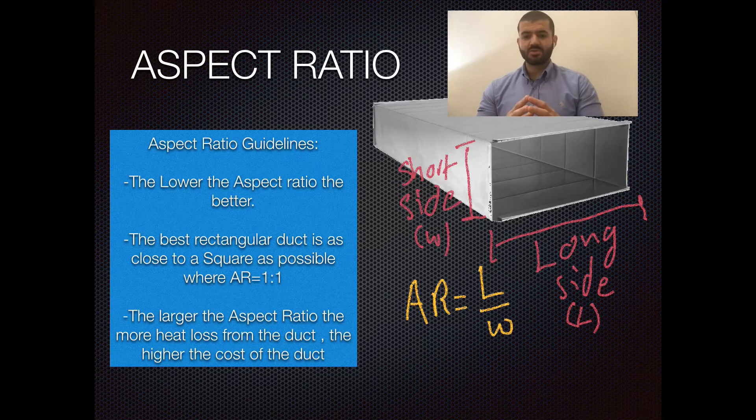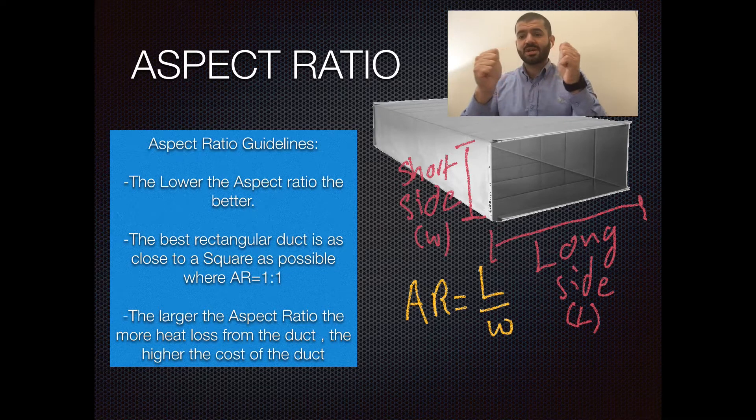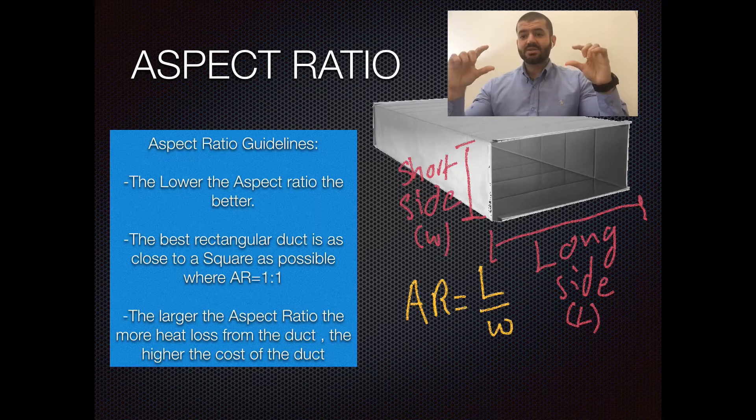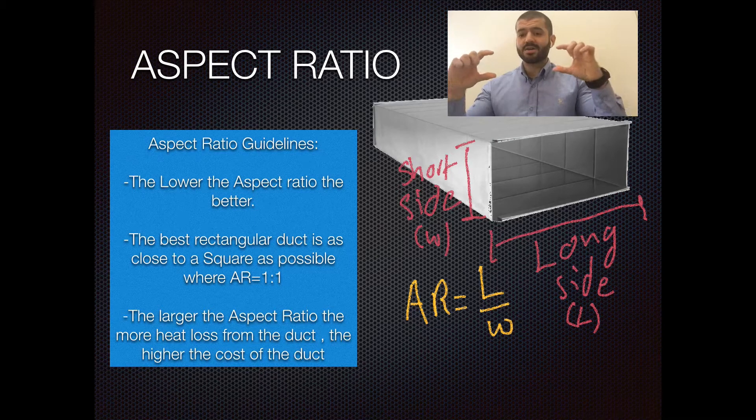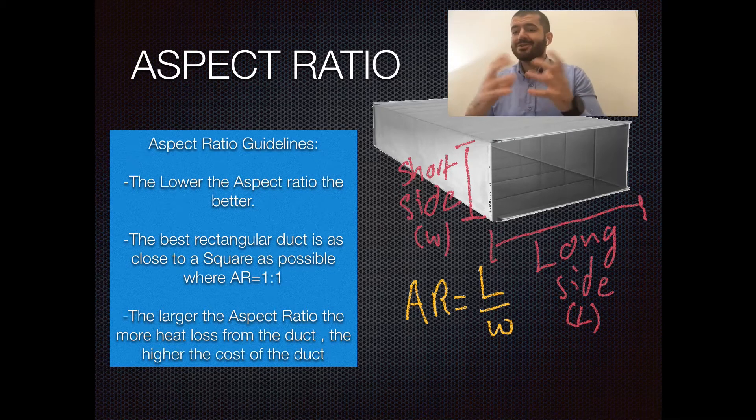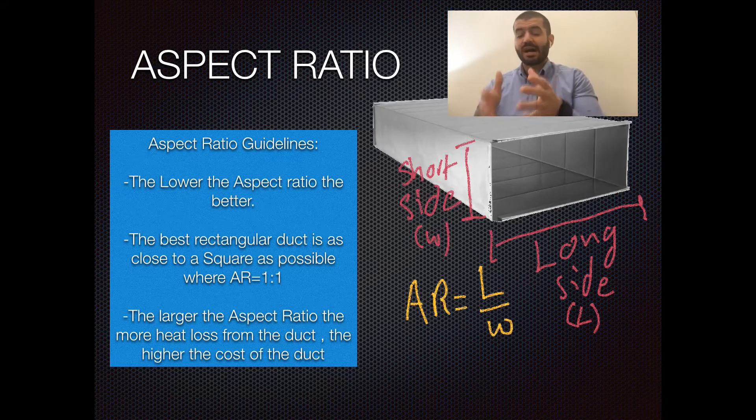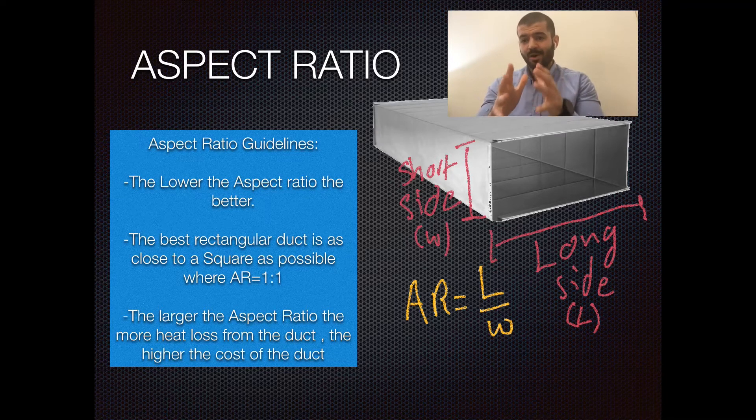Think about it this way. If you have, for example, a rectangular duct and you're stretching it out, what's going to happen to the duct? The width is going to shrink and the length is going to increase, right? However, if we reverse the process, what are you going to have? Both sides almost the same. So the best way to go about this is to have your aspect ratio as close to 1 as possible.